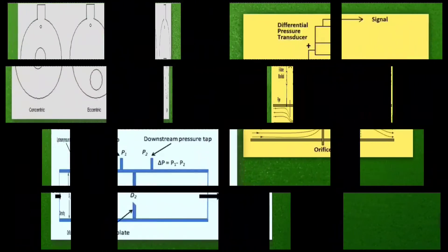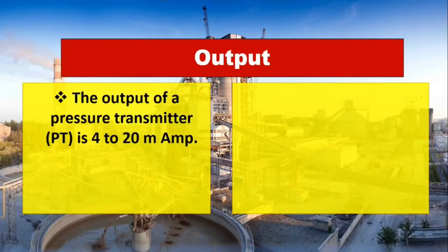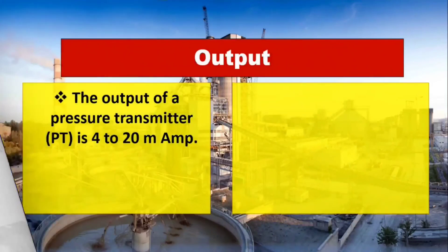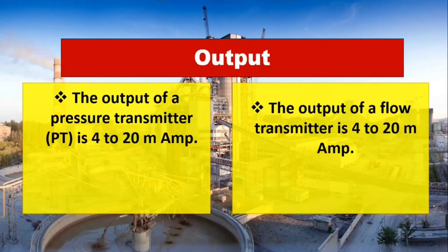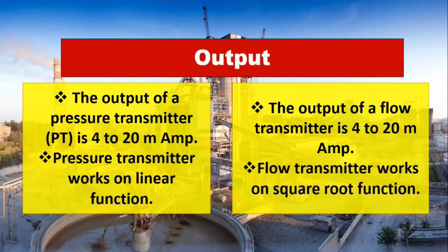The next comparison is output. The output of pressure transmitter is usually 4 to 20 milliampere signal. The output of flow transmitter is also 4 to 20 milliampere signal. Pressure transmitter works on a linear function, whereas flow transmitter works on a square root function. This is a very important difference and you have to keep it in mind.